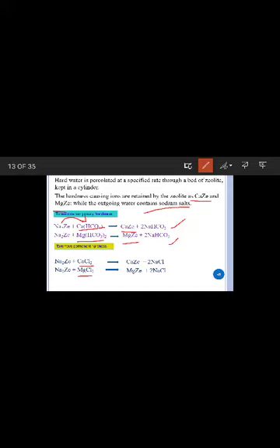When we pass the water containing permanent hardness salts over the sodium zeolite, there will be an exchange. The calcium is converted into calcium zeolite and there will be formation of sodium chloride. In the same way, the magnesium chloride is changed into magnesium zeolite plus NaCl.